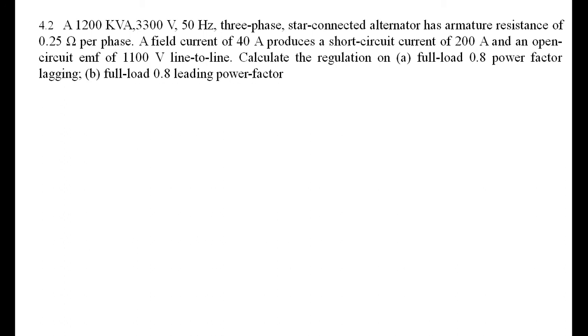Now we take a numerical example. It is a 1200 kVA, 3300 volt, star-connected alternator. Armature resistance Ra = 0.25 Ω. For a field current of 40 amperes, the short circuit current is 200 amperes, and for the same field current the open circuit voltage is 1100 volts (line to line). We are asked to calculate the regulation at 0.8 power factor lagging as well as leading power factor.